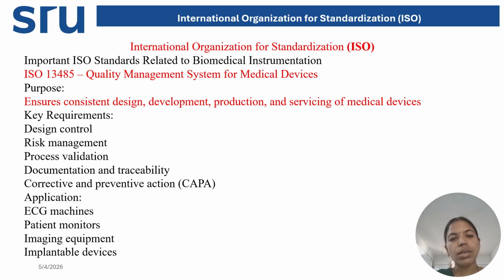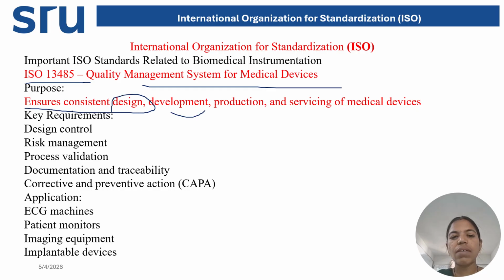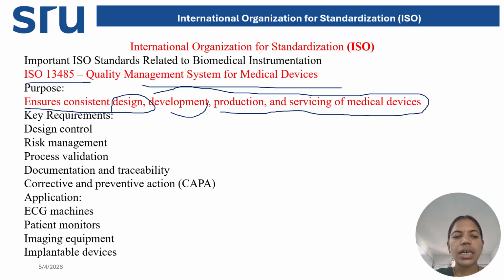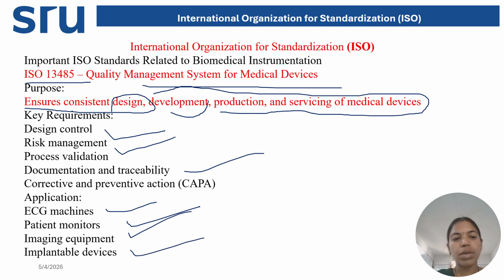So an important standard is ISO 13485, quality management for medical devices. The purpose of this is to ensure consistent design, development, production and servicing of the medical device. Requirements involve design control, risk management and documentation, and the applications are ECG machines, patient monitoring and imaging equipment, and implantable devices.